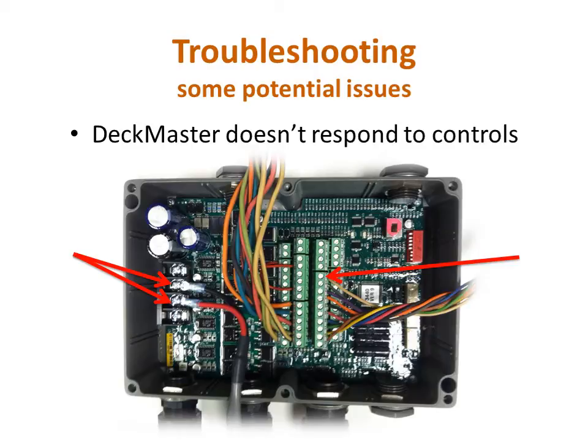If those have power and the controller is functioning properly, then the terminal pin assigned to a given function, for instance TB1 pin 8 for deploy, will get power from the controller when the corresponding switch is pressed. If not, the controller is faulty. If the switch input receives power, but the board does not output power to the corresponding motor, then the board itself is bad.